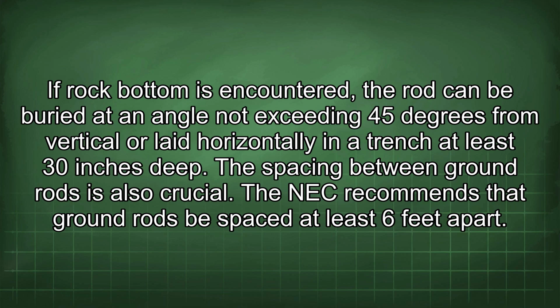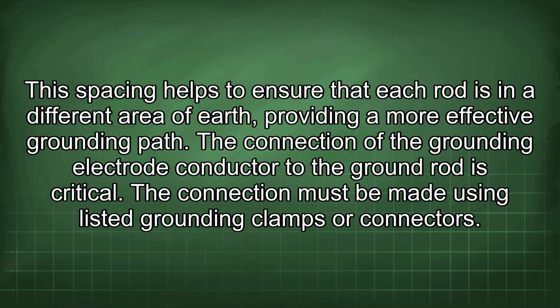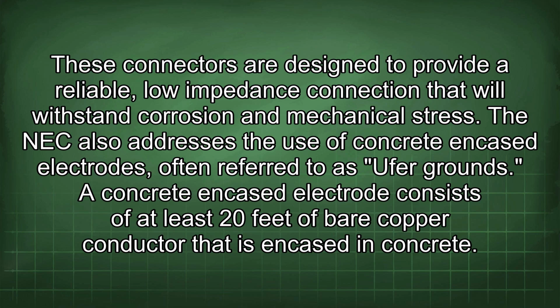The spacing between ground rods is also crucial. The NEC recommends that ground rods be spaced at least 6 feet apart. This spacing helps to ensure that each rod is in a different area of earth, providing a more effective grounding path. The connection of the grounding electrode conductor to the ground rod is critical. The connection must be made using listed grounding clamps or connectors. These connectors are designed to provide a reliable, low-impedance connection that will withstand corrosion and mechanical stress.